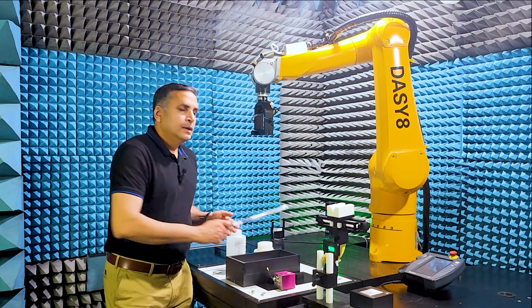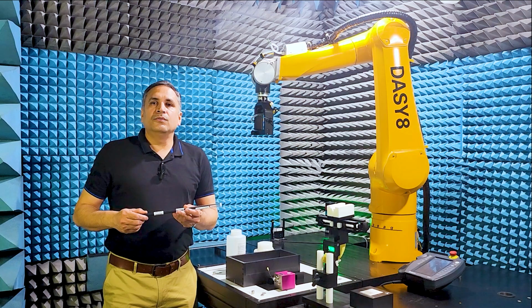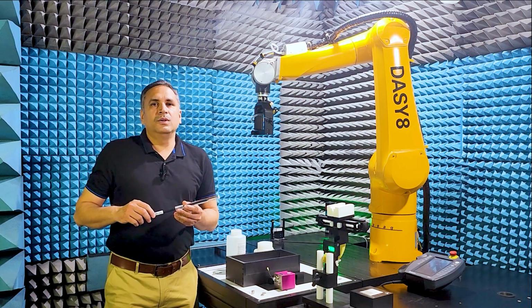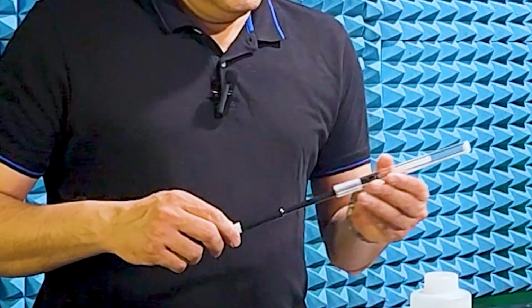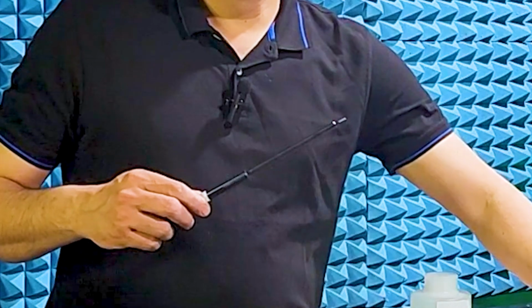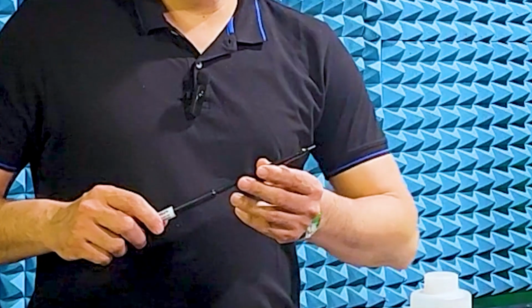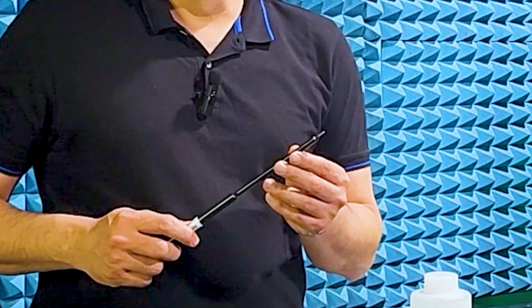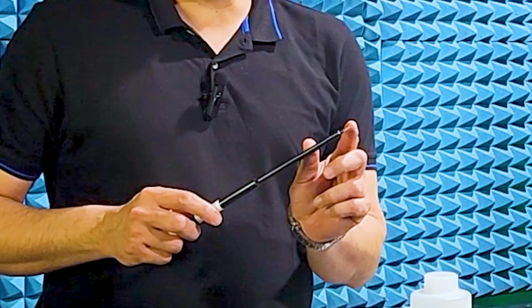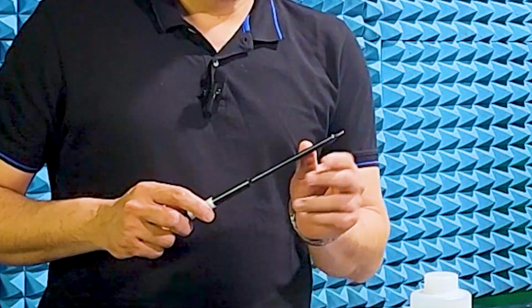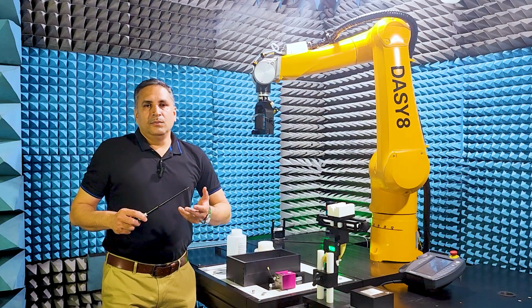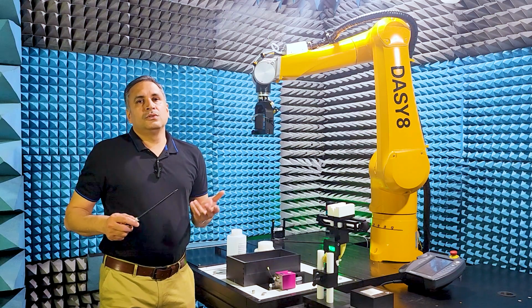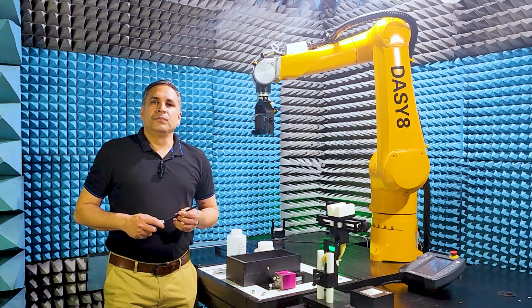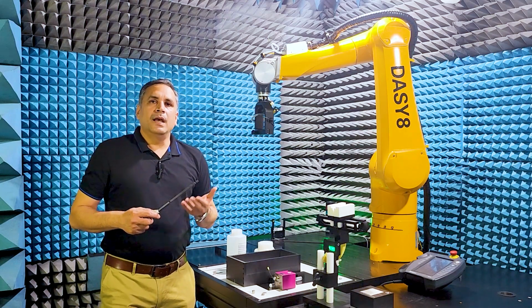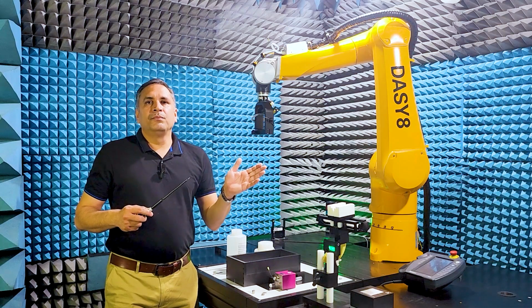First of all, the new APD version 2 probe developed by SPEAG. This probe is based on the same principle as the free space millimeter wave probe, but is encapsulated with a material that has dielectric properties similar to those of the skin simulating material. This design helps to reduce scattering.